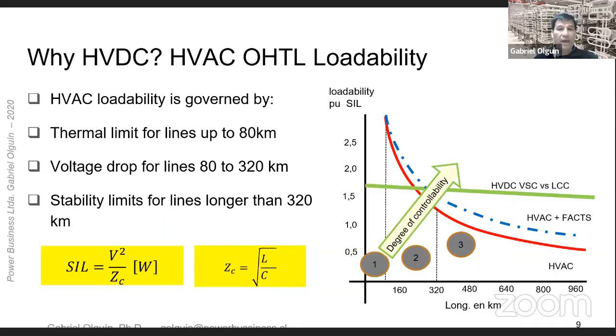Okay, but why HVDC? To explain why HVDC, we can use the so-called loadability curve of an AC transmission line. The concept of loadability is useful in developing a fuller understanding of HVAC power transfer capability as a function of the length of the AC line, as you see in this graph. Line loadability is the degree of line loading expressed as a percentage of the surge impedance load of the line, the SIL, permissible given thermal, voltage drop, and stability limits.